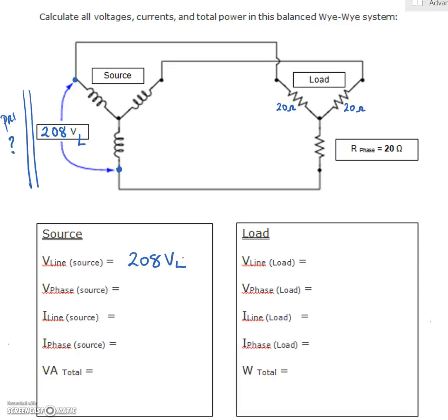I'm doing my videos from Canada. So our distribution systems are quite often a 120/208 volt supply. Other places like the States, you may have a 277/480 volt supply. Others, you may have 347/600. In this case, we've got 208 volts as our line voltage. So that means that the voltage from here to here is 208 volts. That's our line voltage.